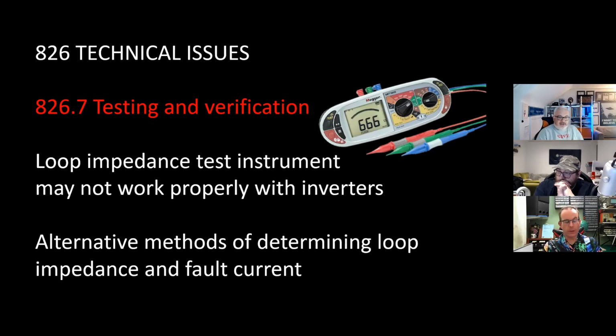Don't think an RCD is going to fix all these problems, because it's not just faults between line and earth. If you have an overload between line and neutral, and the inverter can't supply enough current to trip the device, you could have too much current going through your cabling, causing it to overheat and set on fire.